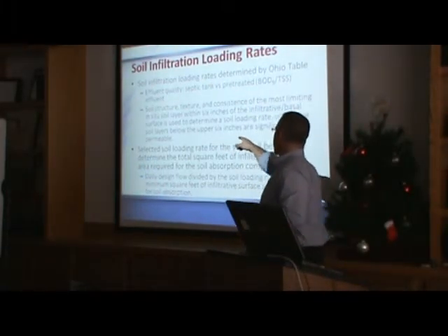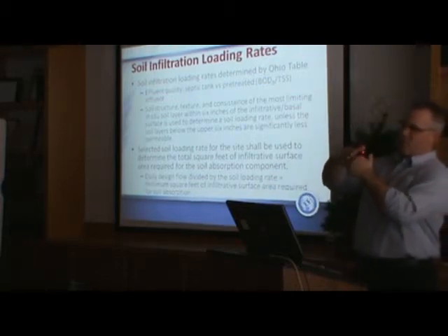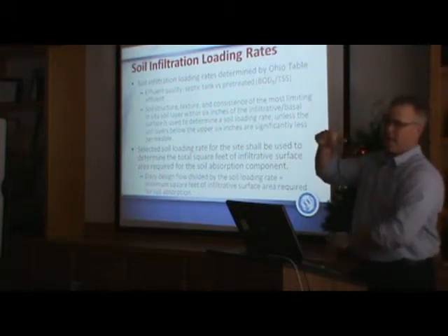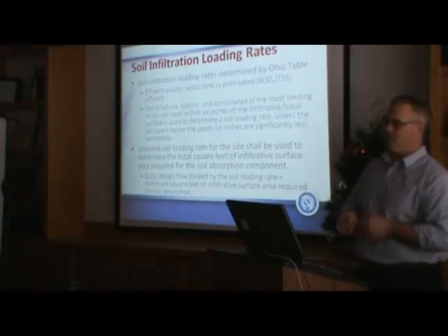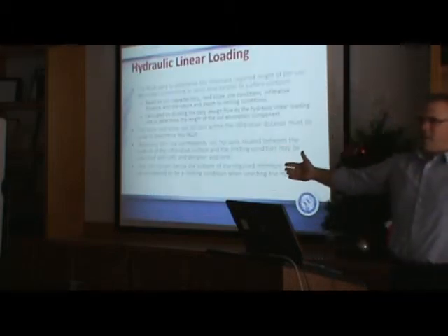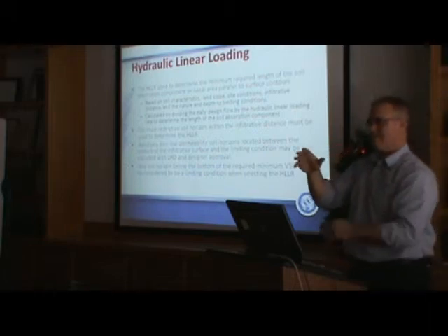And the however is found at the very end here. Below the upper 6 inches, unless it's significantly less permeable. In the past, we would look at, in many cases, 12, 18, 24 inches underneath of that where that water is being applied. But now they're saying the top 6. So that may dictate different square footage of systems. On the other hand, the length is determined by everything until you hit the limiting layer, which is what we're doing for both of them now. So they've kind of made one less strict and kept the one the same. I don't know why, but that's what they're doing there.